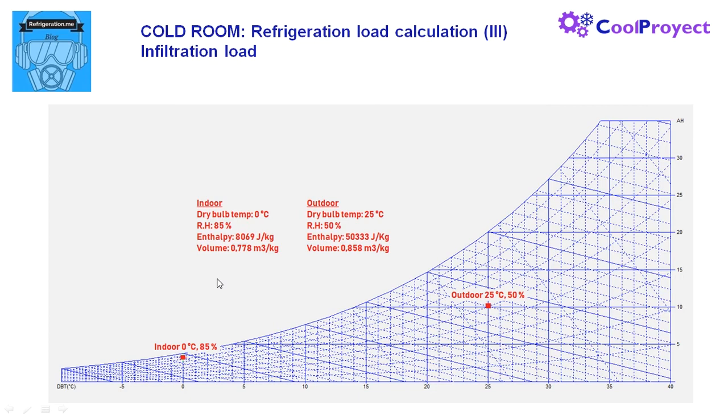For each point we have dry bulb temperature, relative humidity, and enthalpy. For the indoor point it is 8069 joules per kilogram. And for the outdoor point is 50,333 joules per kilogram. We can see that the specific enthalpy or energy of the outdoor air is higher than the one of the indoor air.